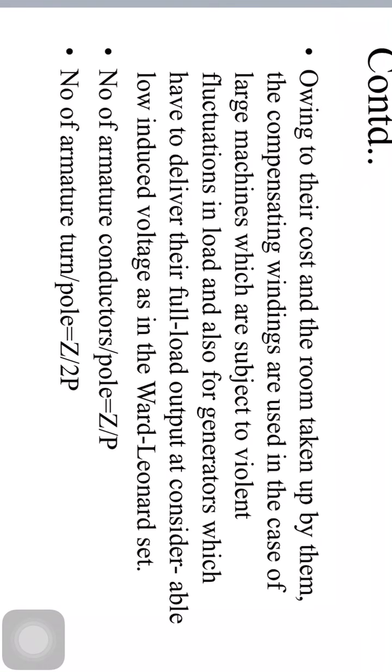These are somewhat costly, and so the compensating windings are used in case of large machines which have very high fluctuations in load, and for generators which have to deliver their full load output at considerably low induced voltage. In such cases we will use this one.